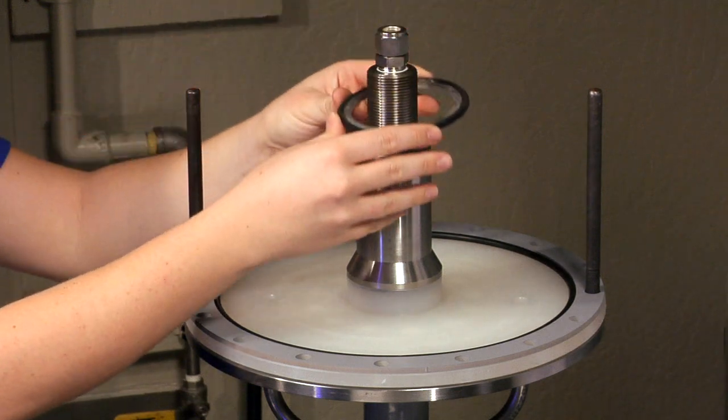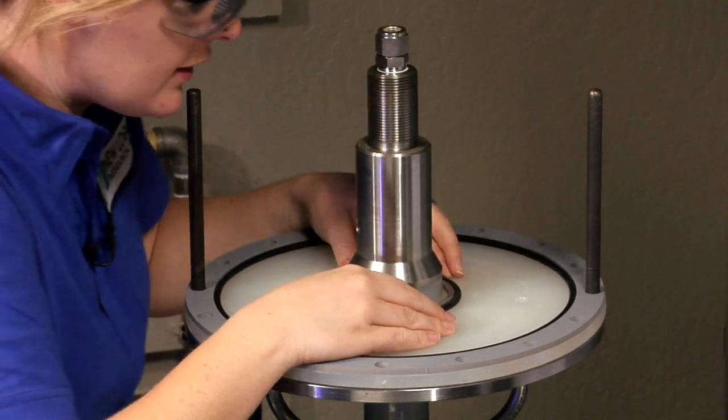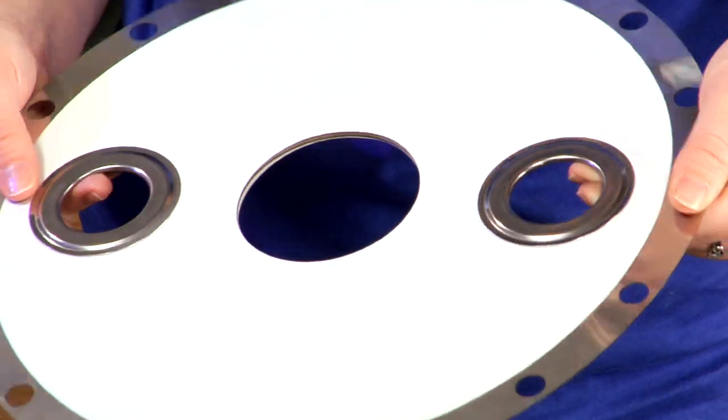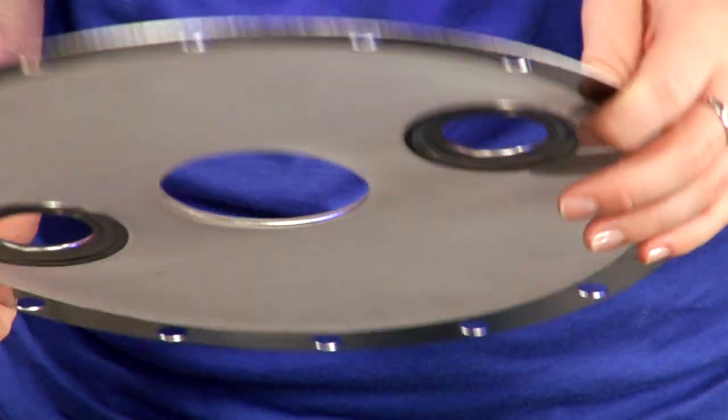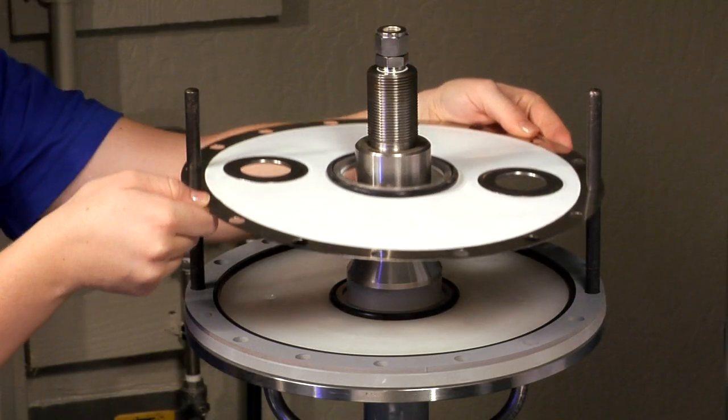Be sure that the inner o-ring and inner retainer ring are concentric with the center shaft. You are now ready for the first membrane tray which should be a regular tray with two open holes. The concave part of the grommet is the bottom and should be facing downward.